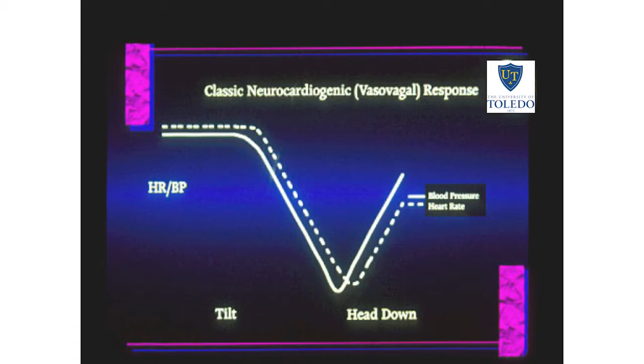Why was that? Well, because during episodes of neurocardiogenic syncope, usually the first thing that happens is they vasodilate all over. And so blood pressure falls first and heart rate falls second. So a traditional pacing device that looks only at rate, by the time it can sense that your rate is dropping, you're already down here. So you're already well into an event. So it comes out being too little too late for some people.